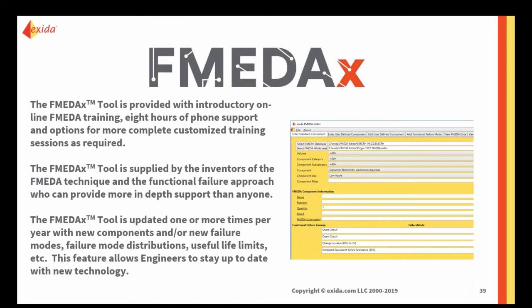Regarding how diagnostic coverage is decided: the FMEDA tool has a database of diagnostic techniques and expected diagnostic coverage factors for well-known techniques, like different kinds of memory tests, ECC, and many others — all built into the tool. It's primarily based on the diagnostic coverage factors from IEC 61508, which we use as guidance.